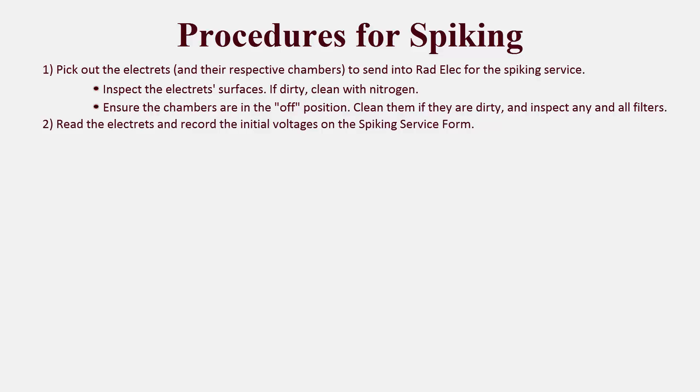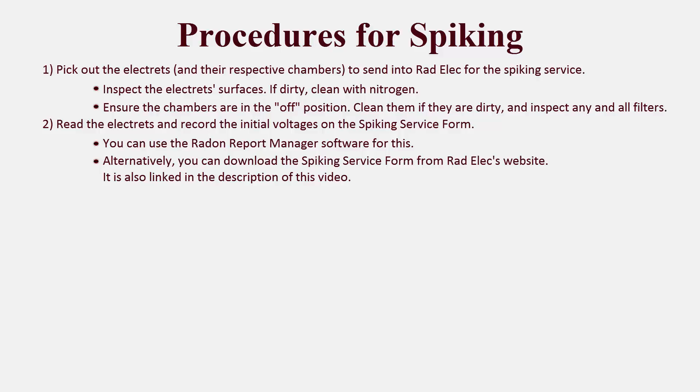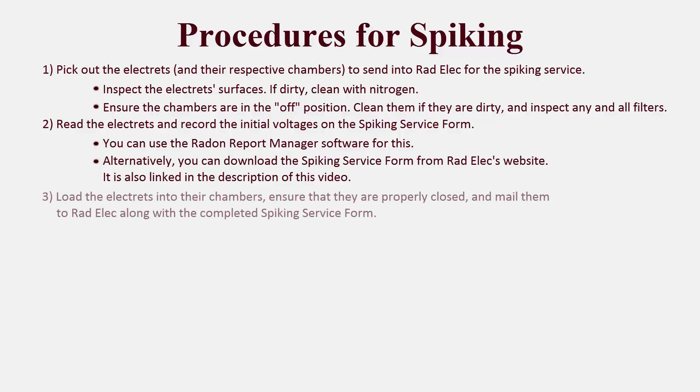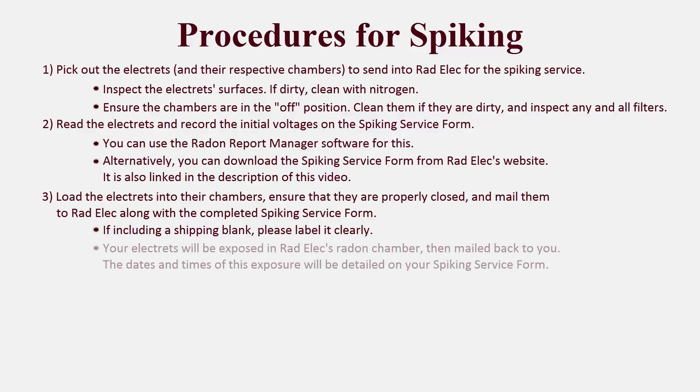The second step is to read the electrets and record the initial voltages on the spiking service form. You can use the Radon Report Manager for this step, or download the spiking service form directly from Radelec's website. Step three is to load the electrets into their chambers, ensure that they are properly closed, and then mail them back to Radelec along with the completed spiking service form. If you are including a shipping blank that is not going to be exposed in the radon chamber, please label it clearly. Once we receive your electrets, we will expose them in Radelec's radon chamber. We perform spiking twice per week, beginning on Monday and Wednesday afternoons, and each exposure lasts 48 hours. As soon as we remove your electrets, they will be mailed back to you.